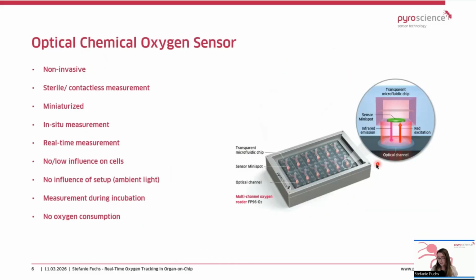So there we have contactless measurement, so we can really miniaturize the sensors, put them directly into the system, and then they can be excited with the same light which comes from the fireplate as in the example before. The good thing about this is we can really get it in situ, close to the cells, get a very fast real-time measurement, and also everything inside the chip can be sterilized. So you don't need to worry about sterility because everything in here is sterile, and the readout is just through the transparent chip material, so there is no way that there will be any ingress of a contamination due to that or any leakage. So with this, we have a really robust system in combination with what I mentioned before, the robust readout method and the no influence on the cells, no oxygen consumption. There should actually be nothing that is interfering with the cell culture at all.